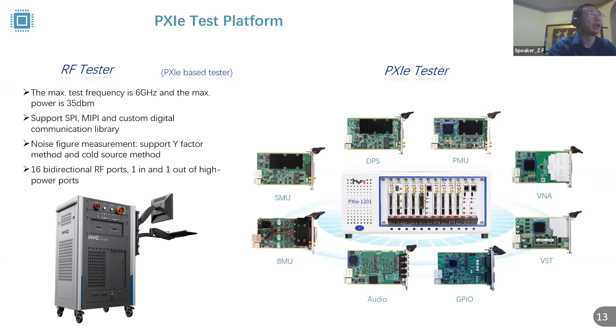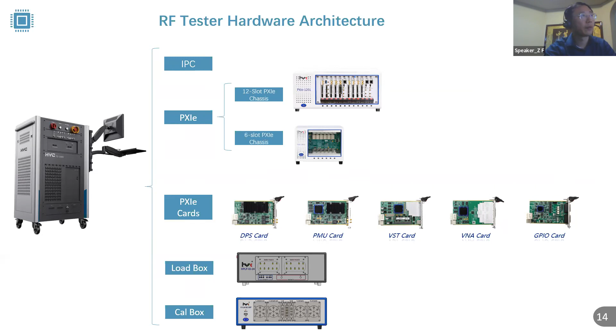Looking into the whole tester as a system, it has the industrial PC, and there are 2 options for PXI chassis inside the tester. One is the 12 slot, the other is 6 slot for fewer resources. PXI cards, as I mentioned, are the variety of functional cards. Also, there's a load box in the tester providing reconfiguration of the resources and also port switching. The calibration box is paired with all the testers, providing calibration on both frequency and power, and also the typical VNA calibration.